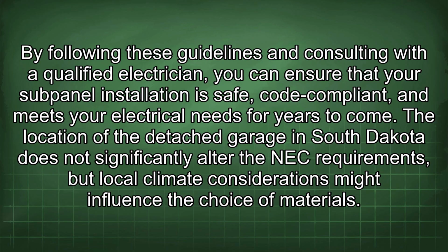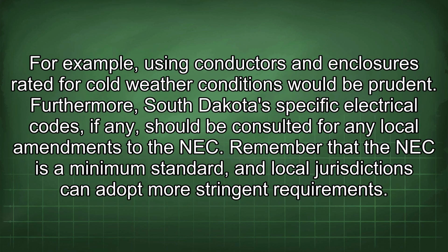The location of the detached garage in South Dakota does not significantly alter the NEC requirements, but local climate considerations might influence the choice of materials. For example, using conductors and enclosures rated for cold weather conditions would be prudent. Furthermore, South Dakota's specific electrical codes, if any, should be consulted for any local amendments to the NEC. Remember that the NEC is a minimum standard, and local jurisdictions can adopt more stringent requirements.